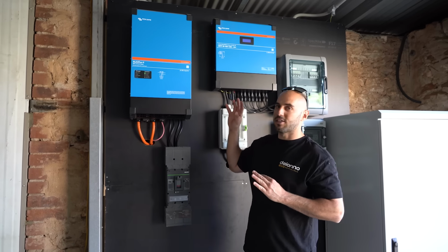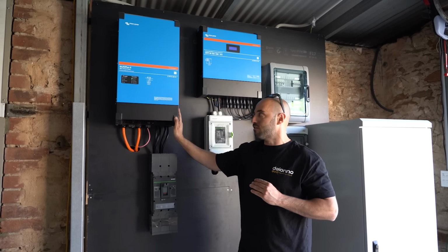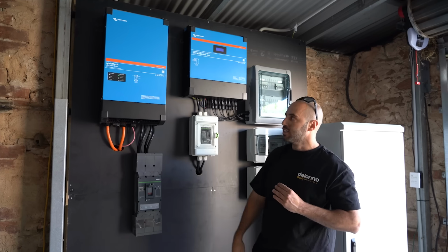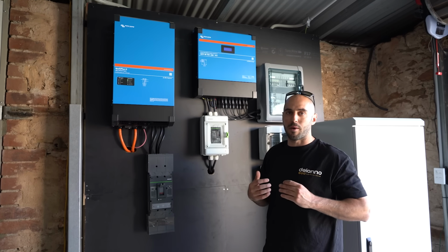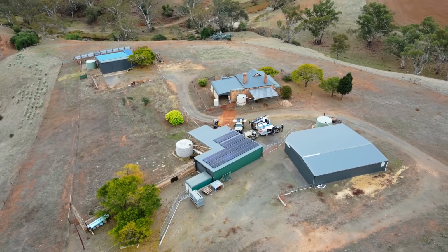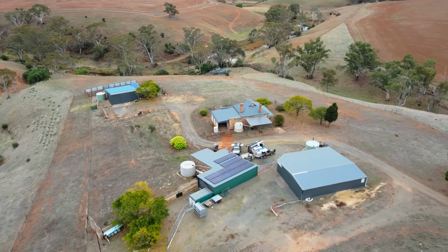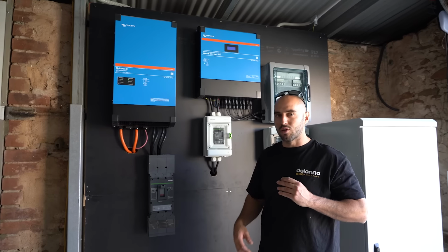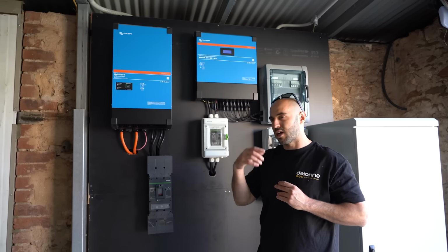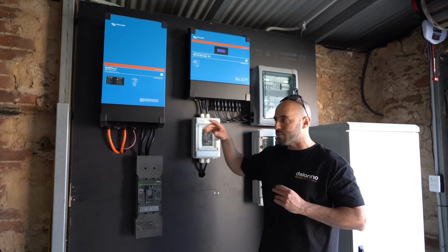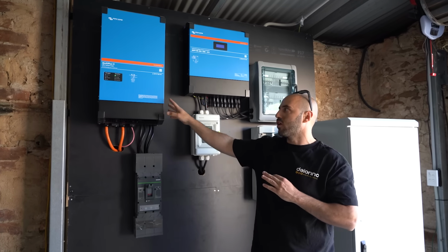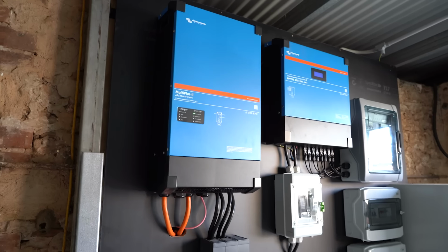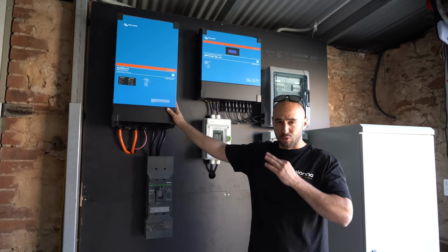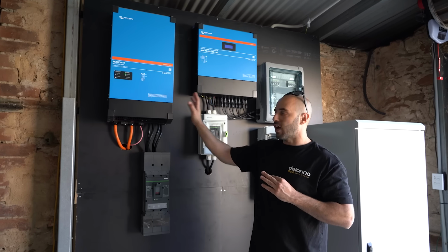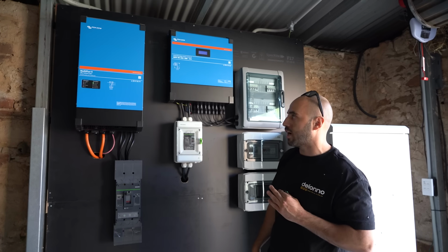All right guys, wrapping up, we've got the MultiPlus 2. This is a 48 volt, 10 kVA inverter charger. This unit is able to take power from our battery stack and provide 10 kVA of output power to our loads, to the house, to the shed, throughout the whole property. It's not a huge property, not a huge demand here, so 10 kVA is good. They do make another size up to 15 kVA, and then go down from there. So this is a good mid-range unit. It can accept one AC input, so if you've got a generator, that AC input from the gen set will convert back down to a 48 volt supply to charge our stack of batteries. Really robust, good unit, has a really high surge rating because it's got a transformer inside. Love these things. This is the main component of an off-grid system, especially with the Victron one.